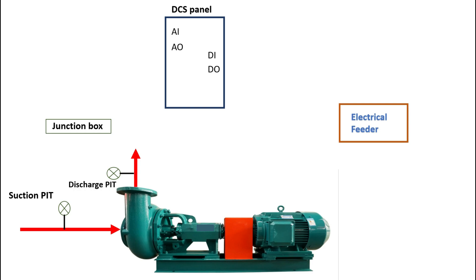We also have an electrical feeder which controls the motor through control supply signals from instrumentation. Basically, from the pump the analog input signals — that is suction and discharge pressure transmitters — go into the junction box. From the junction box, a multi-core cable runs to the ICS rack room and gets into the analog input module.